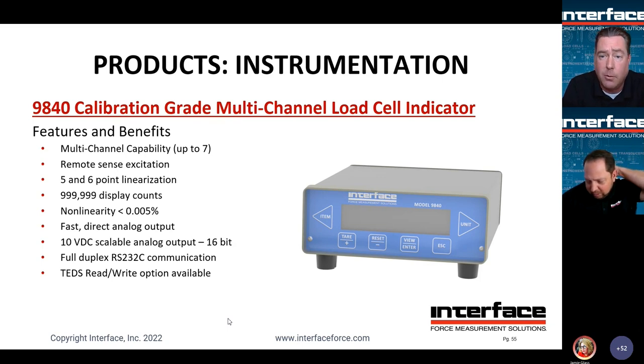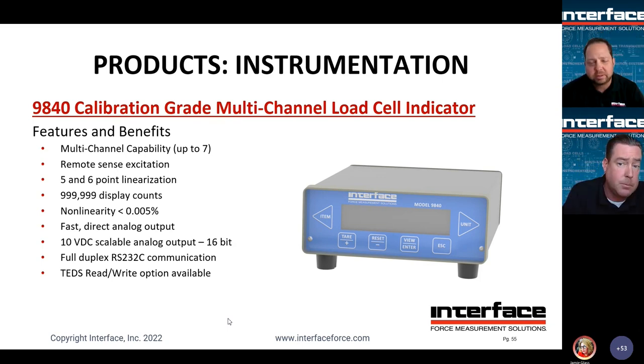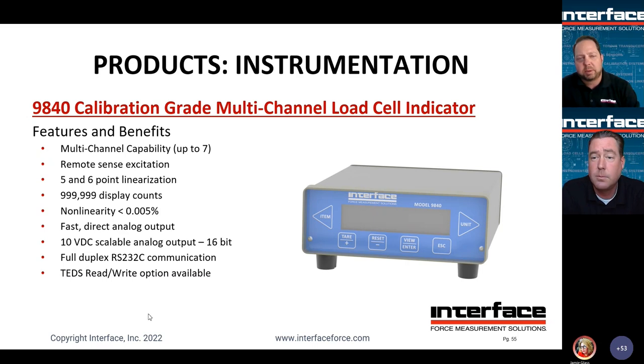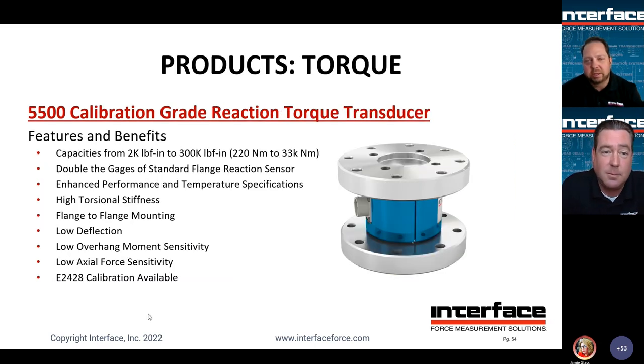9840. Just real quick on the flange sensor, back up one slide real quick, Jamie. Elliot touched on the fact we may increase bolt holes, and that is to ensure that there's adequate clamping force. It's real important for users to understand that torque is transferred through that clamping pressure and not through shear loads through the actual bolts, right? So want to make sure everyone's aware of that.